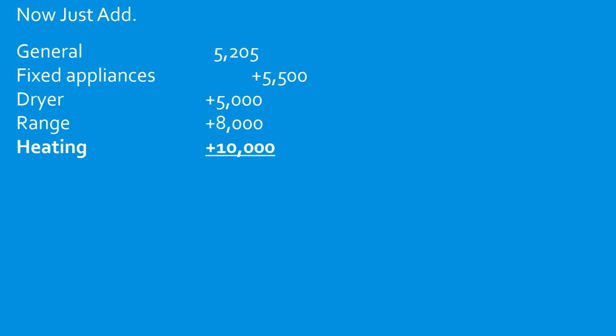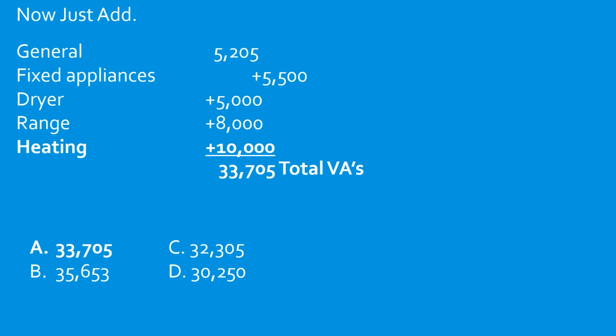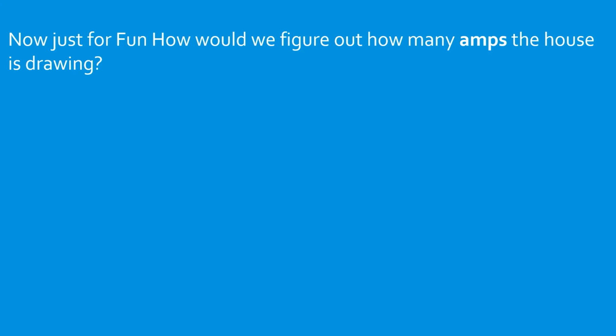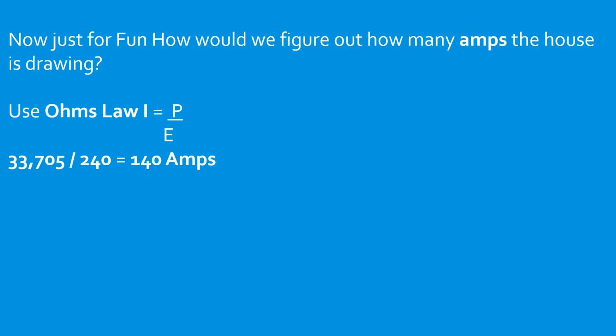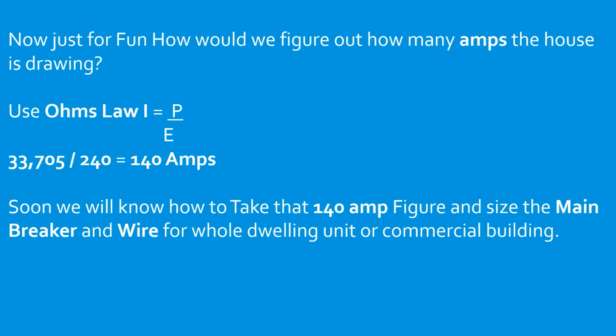Now we just add them together. We take our general, fixed appliances, dryer, range, and our heating, add them together, and that's going to give us 33,705 total VAs. And we select A. Now, just for fun, how would we figure out how many amps the house is drawing? We use our Ohm's law. Okay, we have 33,705 VAs. We're going to divide it by the system voltage, and that is going to give us 140 amps. Soon you'll know how to take that 140 amp figure, size the main breaker and the wire for a whole dwelling unit or commercial building.